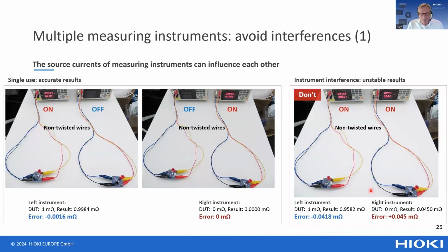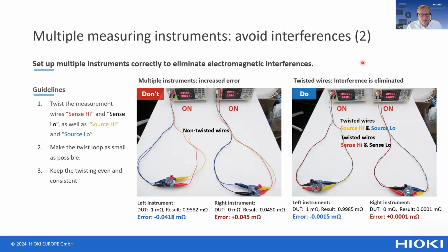Another cause of a problem might be that you are using multiple instruments at the same location in the production line. It is possible that the test current resulting from one instrument can influence the measurement of another instrument. Probably you have already figured out that also in this case the solution is to twist the wires. You can see here, in the situation where we have twisted the wires of both of the instruments, there is almost no error measured with the two measurement instruments. And that's showing that twisting the wires is solving a lot of issues that are related to electromagnetic induction in the production line.